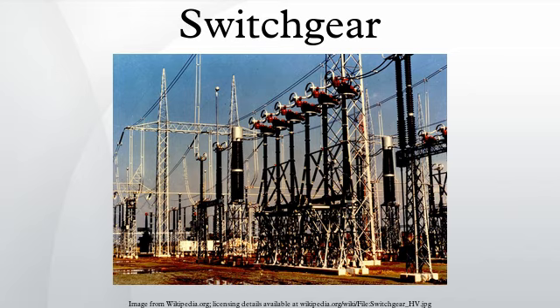The increasing awareness of dangers associated with high fault levels has resulted in network operators specifying closed-door operation for operating earth switches and racking breakers. Many European power companies have banned operators from switch rooms while operating. Remote racking systems are available which allow an operator to rack switchgear from a remote location without the need to wear a protective arc flash hazard suit.